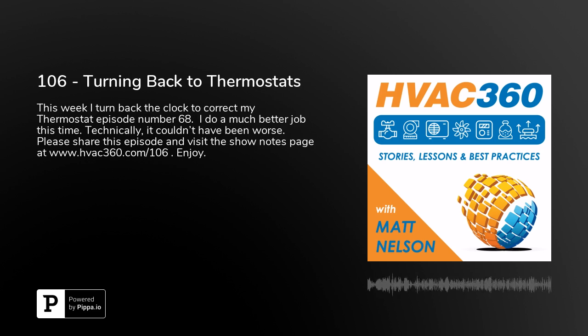There are other cases where you're at that thermostat and you're setting the two parameters. You're not picking the one in the middle, but you're saying, okay, in heating mode, I'm going to be at 68. So whenever the box is in heating mode, that's the only thing that you're going to see on the sensor on the wall, and you're going to modulate that set point. So again, it's different every time you approach that stat, exactly what the control sequence is. And that's why it's good to be able to talk to the temperature controls contractor to figure that out and identify that. Because they're all slightly different. And as many times as I've looked at it, every time I'm like, okay, how is this one working?